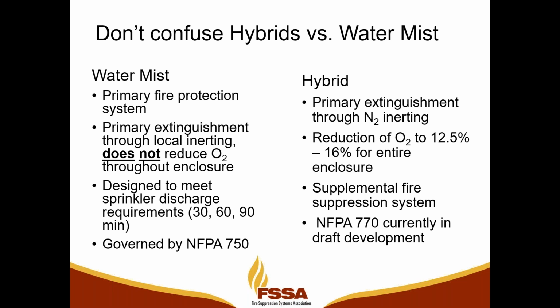In a hybrid type of system, the primary extinguishment is through N2 inerting, or nitrogen inerting, which is lowering the oxygen levels to between 12 and 16%. But it's also a supplemental fire suppression system. What we mean by that is, when I talk about a primary fire protection system, I said we can take a water mist system and replace a sprinkler system in that same space, for example, in a data center or an industrial complex, protecting certain machinery and those types of things.